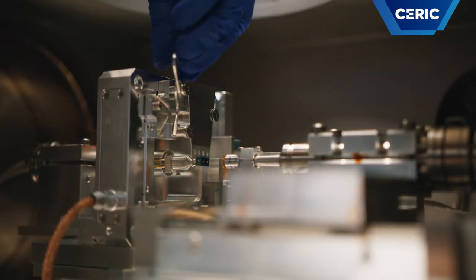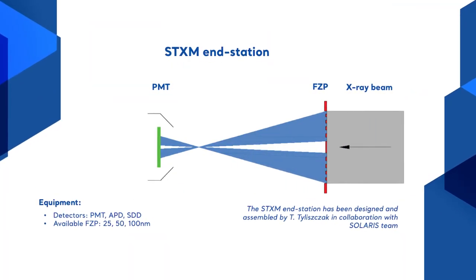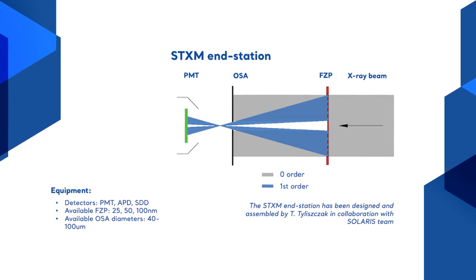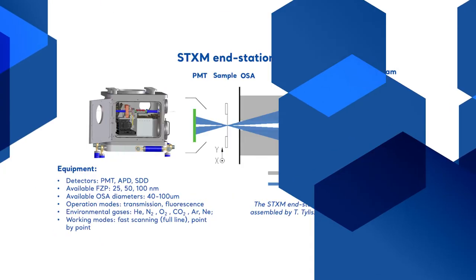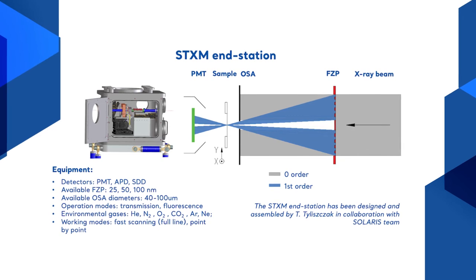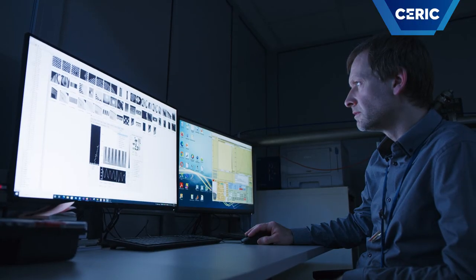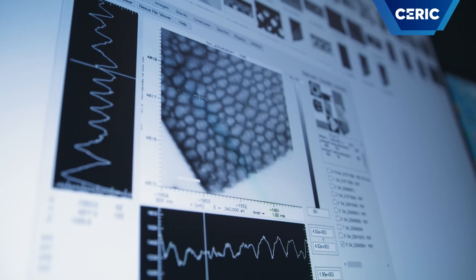One of the main elements of the STXM microscope is the Fresnel Zone Plate. The FZP focuses the monochromatic beam of photons delivered by the synchrotron. After passing through the Fresnel lens, the photon beam passes through the aperture used to select the diffraction orders of the specific order. The sample is located at the focal point of the Fresnel lens. The sample position is raster scanned with a piezoelectric scanner and monitored with laser interferometric sensors. By collecting scanned maps as a function of photon energy, we can obtain image stacks. By analyzing them, we can get information about the chemical properties of the elements of interest.